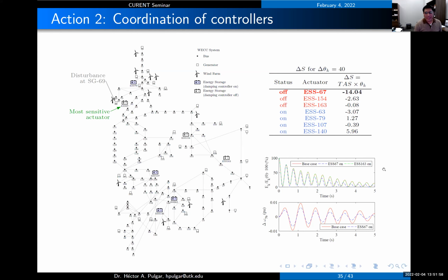So we tested this in the WECC system. You have 179 buses here and several generators, and we have controllers, and we assume that these controllers came from energy storage devices. We enable some controllers in these 4 energy storage, and these 3 were disabled. In that system, you have a disturbance in this bus, and then you determine the sensitivities, and you realize that the control actuator in this controller that is off is actually the most sensitive and needs to be turned on. By doing that, you can see the improvement in the oscillation. The system responds better when you turn on that controller.